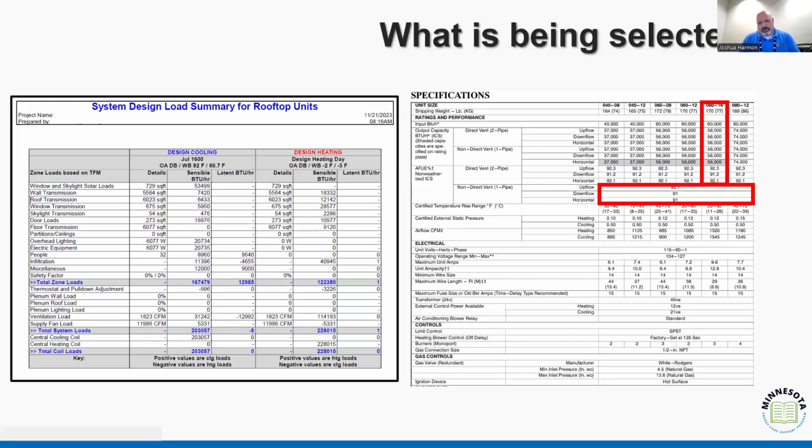And a lot of times what we see is, especially the first thing that happens before a business, again, we've talked about these on large scales. If I'm expecting a $20,000 a month expense for operating costs and I'm getting $60,000, the first thing I'm going to do is call another engineer, call another mechanical person out and say, evaluate this system, tell me what's wrong with it. And if it comes down to, well, they were supposed to put in round duct, but they put in flex line, and so your system is operating twice as hard to get the air to the right places to change the temperature, then that comes back to somebody in this circle, to who is supposed to acknowledge or identify that. Is it always us?